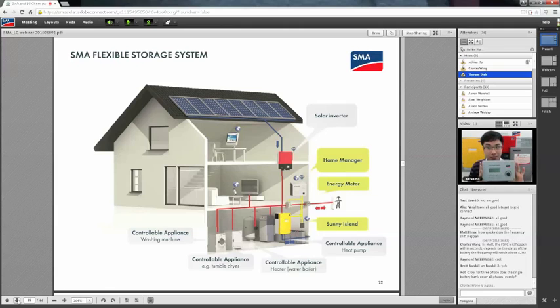For a sunny island system, you always need the remote to commission the system, whether on-grid or off-grid. Check in the order whether this is included. Without the remote, there's basically nothing you can program, there's just 3 buttons here, you can't program anything or start the system at all. You must have the sunny remote control.